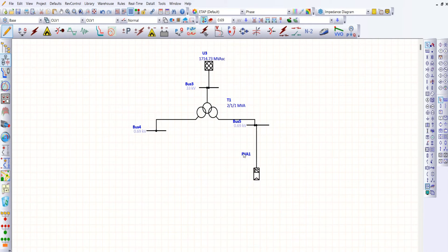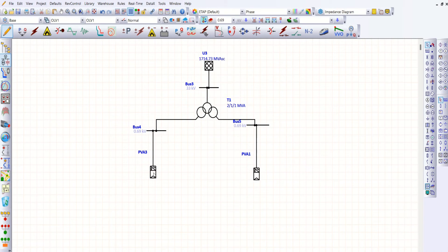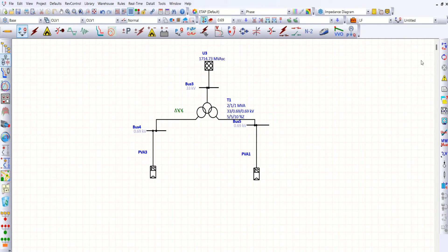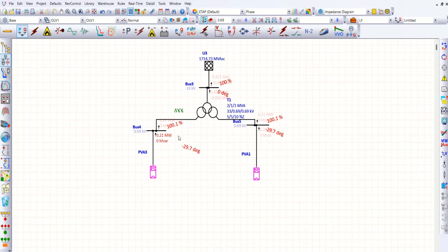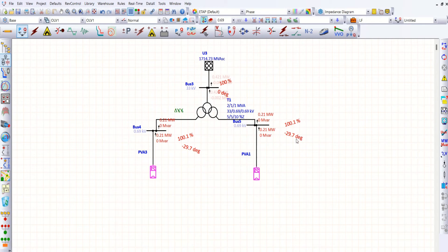Similarly, I want one more array. I am copy-pasting this PV array, so both have the same rating. Now let me run load flow and cross-check the result. Load flow is running. Now you can see the results here. Voltage maintained at this bus is 100.1% with an angle of minus 29.7 degrees, and the same for the other bus as well since we have connected the same rated PV.